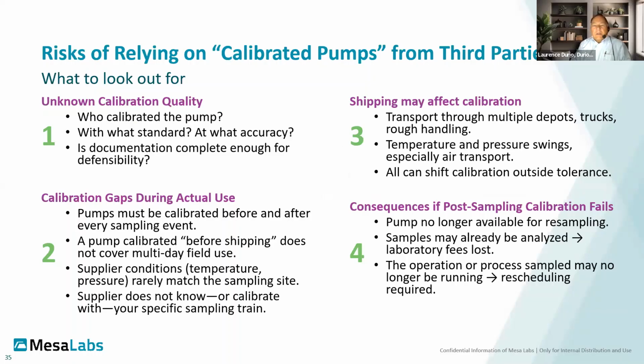What I see a lot now is the use of pumps from third parties, either rental or laboratories. I don't have a problem with this. Save the money if somebody is going to lend you pumps. If you're going to do something just once or twice, renting is probably cheaper than buying, but they've got to be calibrated, just like a pump you own. You need to know who calibrated it, with what standard, and you need to be able to get that documentation. After it's done at a remote location, it's shipped to you. Rough handling, vehicles, airplanes, all of this can shift the calibration, even if it doesn't shift it when it gets to you. Sending it back can shift it on the way back.